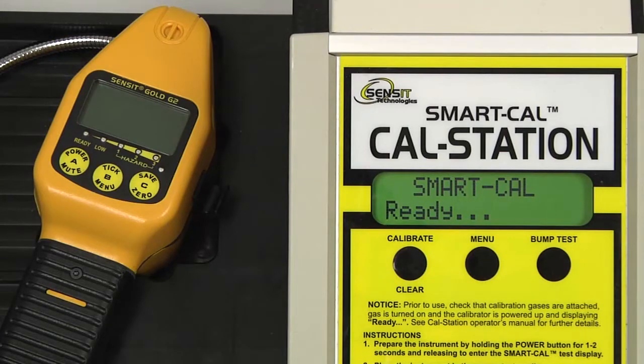To begin, ensure that the cal station is plugged in and is displaying SMART-CAL Ready on the screen, and power on the G2 by pressing and holding the A button until the SENSIT logo appears. Allow the instrument to complete the entire warm-up cycle and arrive at the working display. After the warm-up process has completed, allow the instrument to warm up for an additional 5 minutes before calibrating.